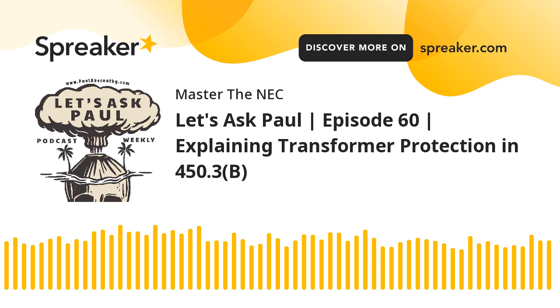Okay, so that means if I have a panel and I have an overcurrent device, which is required to protect that panel guts, we call the panel board, the cabinet is what the panel board goes into, and we have a breaker in there. That is protecting the panel board, okay? And it falls under the rules of 408.